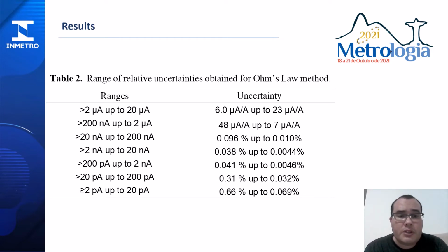This table shows the relative uncertainty values for each range using the Ohm's law method. It was possible to obtain uncertainties between 6 microamperes up to 23 microamperes per ampere in the range of 2 microamperes up to 20 microamperes. In the range of 200 nanoamperes up to 2 microamperes, the uncertainty obtained was 48 microamperes per ampere up to 7 microamperes per ampere.